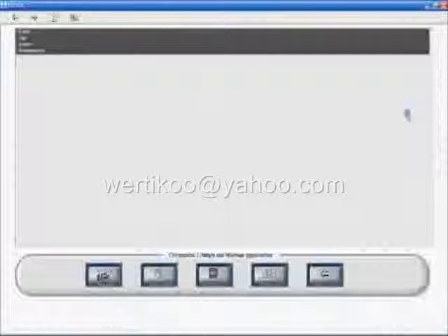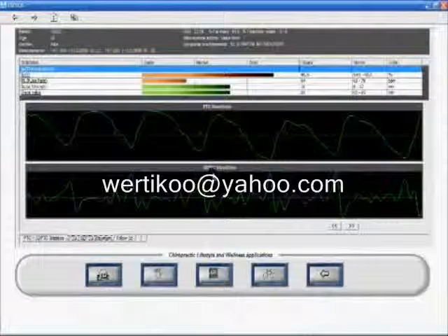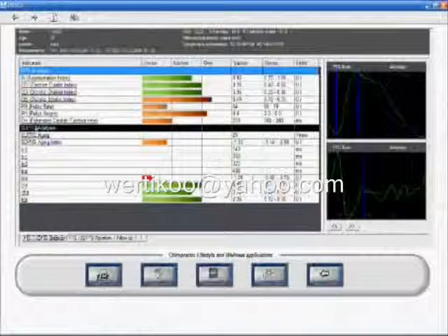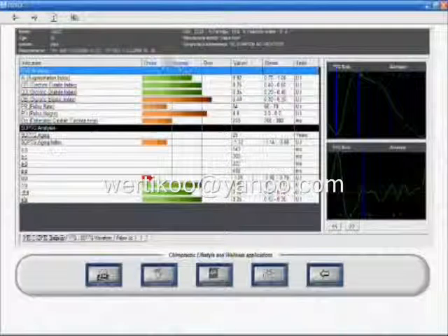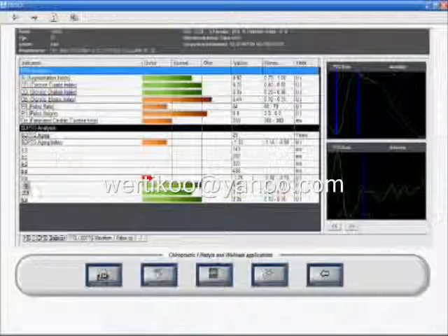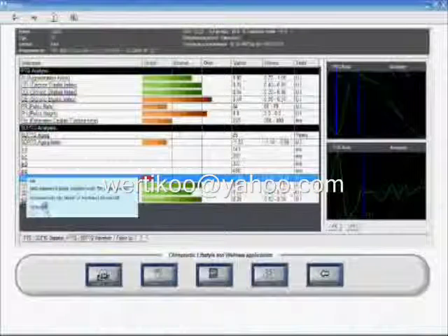The oximeter provides SpO2% with the original wave PTG and the acceleration of this wave named second derivative plethysmograph waveform. The analysis of the PTG and SD-PTG provides a list of indicators, also displayed with the scale, value, normal range, and unit. Here, for example, the ratio -DA is one indicator of hypertension, and the ratio BA is an indicator of the heart left ventricle function.